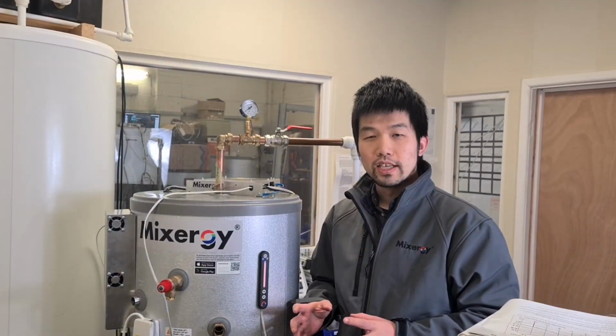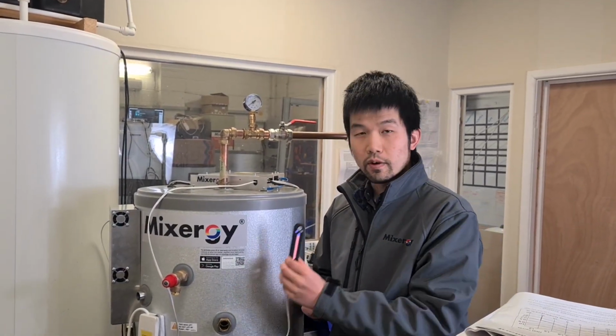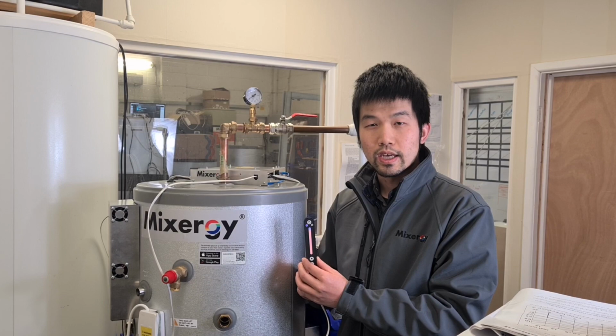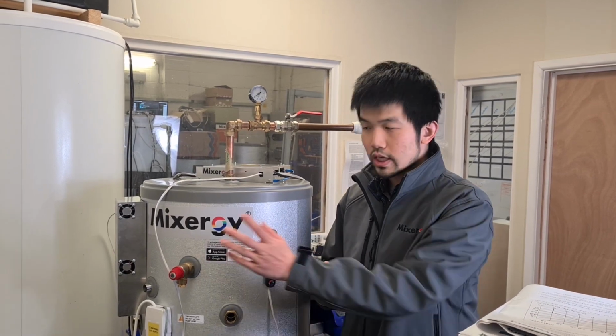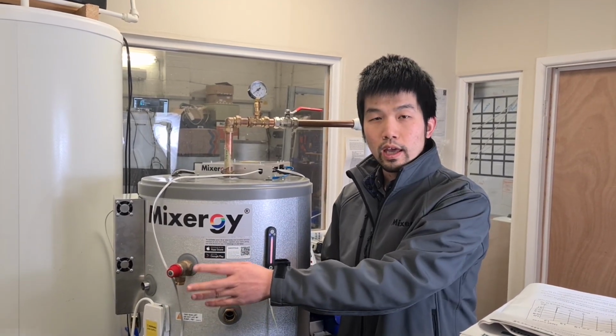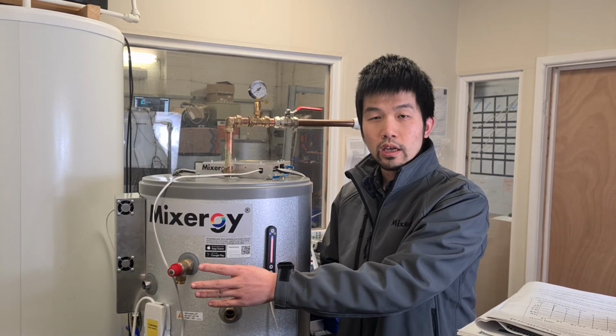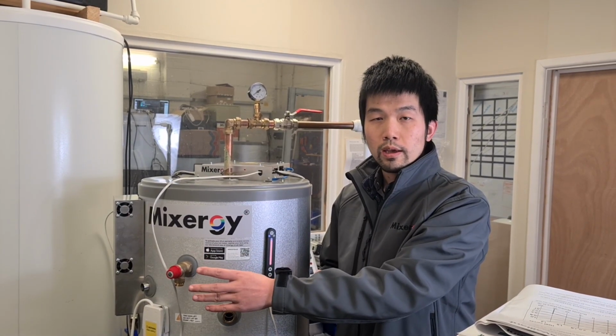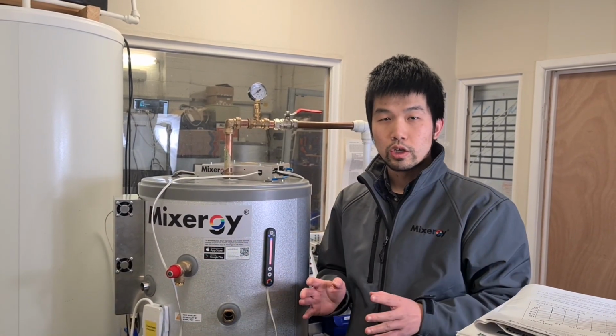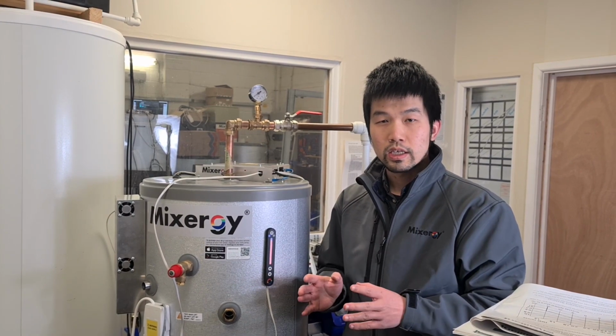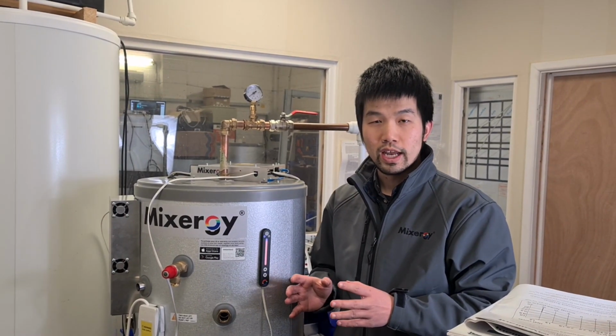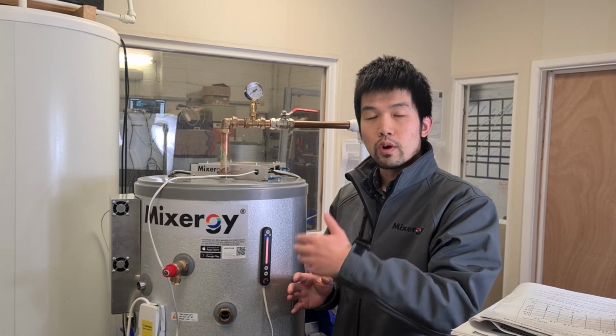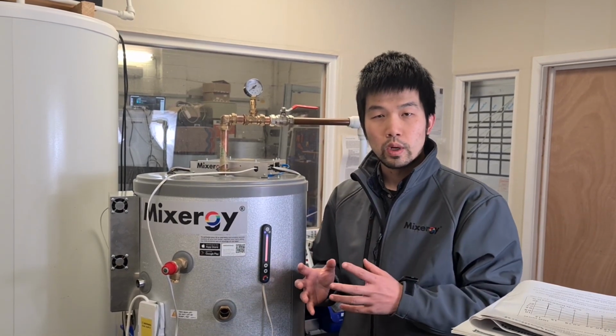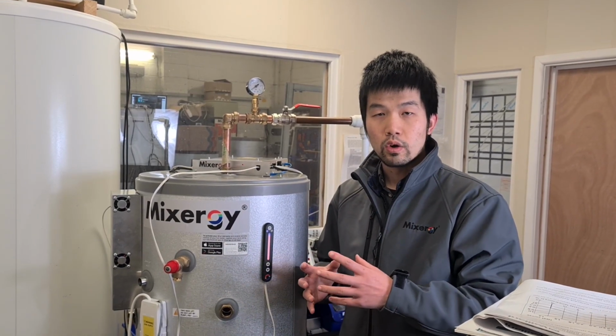The heat pump cylinder has finished its heating, as you can see from the gauge that is showing 100% charge. So based on the reading of the heat panel, it's giving a COP of about 1.2. But bear in mind, it's -1 degree outside and it's humid, and you have frost building up around the radiators. So throughout the seasons, with better weather conditions, we'll be expecting around 2 to 3 COP.